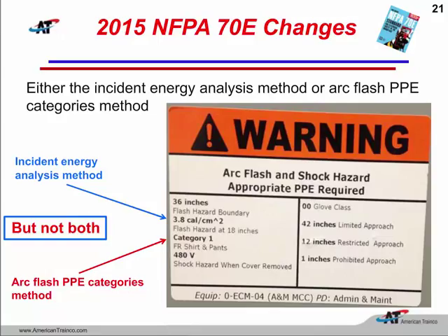And, of course, the 2015 70E is already being enforced. So we're going to have to take a look at our arc flash analysis method. We have to review that every 5 years. If we do find a conflict with the label, they would like to have us update the labels. So you're going to have to take a look at your labels and see if in fact you do have both of these methods listed on the label. So depending on the software that was used or how the electrical engineer decided to generate their labels, you might see this on some of your labels out there. As the labels are reviewed, we're going to probably, if it's an analysis method, only see the incident energy on the labels. We won't see a category on there going forward.